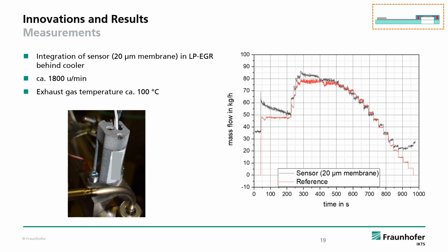The sensor shows every change of the gas mass flow very precisely. It is seen how the black curve follows the red one. Slight differences are seen in the absolute mass flow value. At the first step, at about 46 kg per hour, the black curve is drifting away. The smaller steps show no drifting and have stable values, but different from the reference. That could be a calibration error. The drifting in the first step has to be analyzed further, to see whether the sensor is really drifting or the mass flow really decreases.